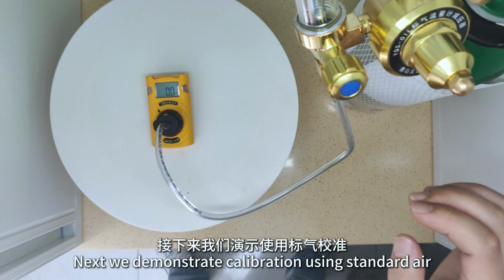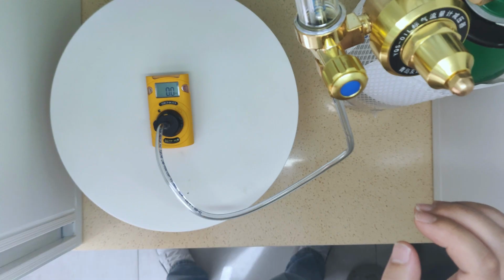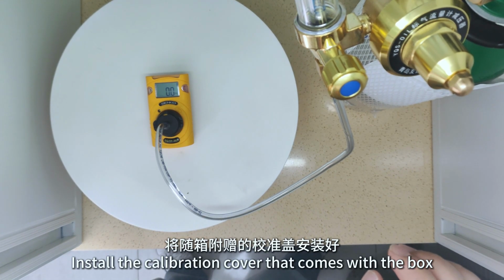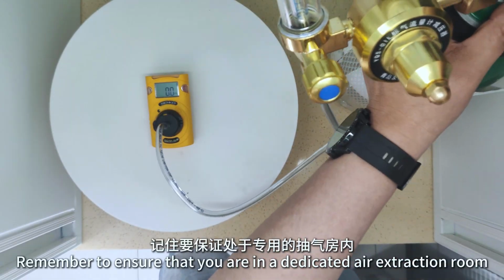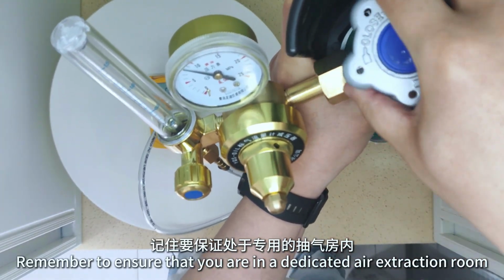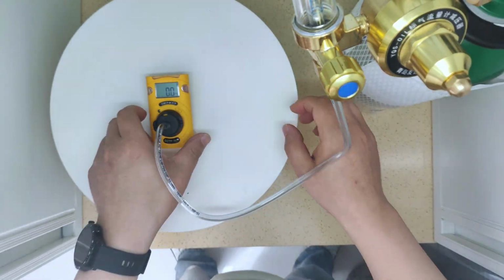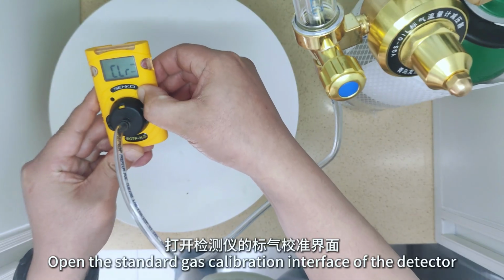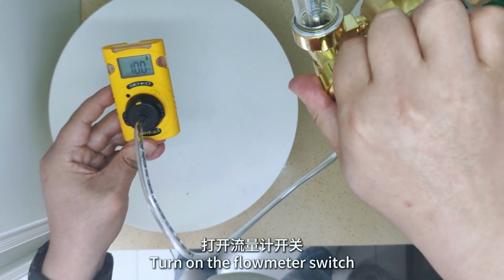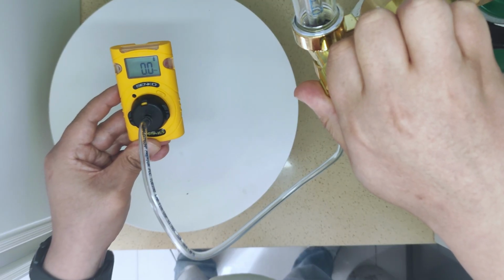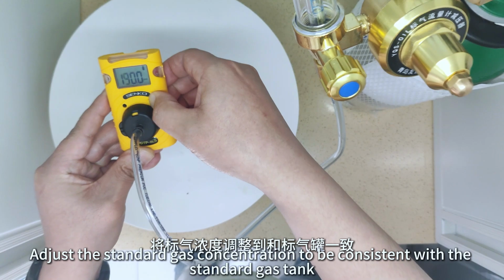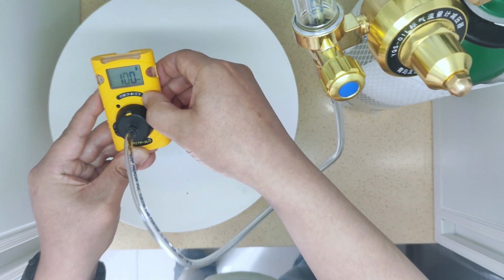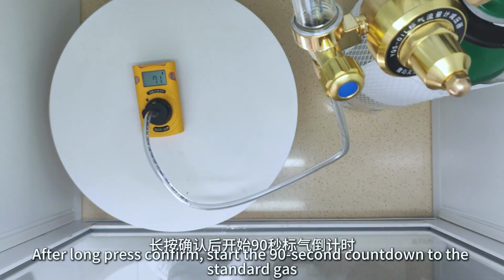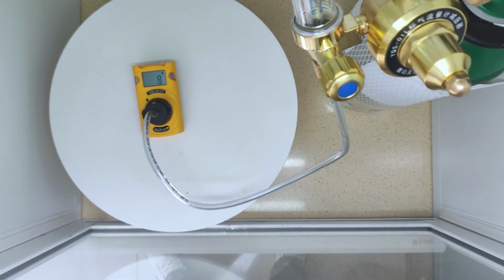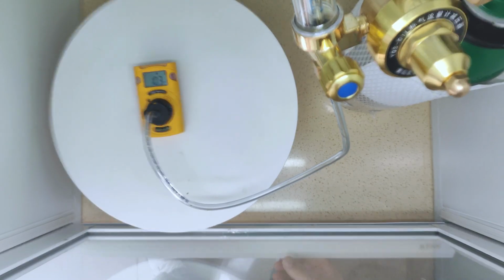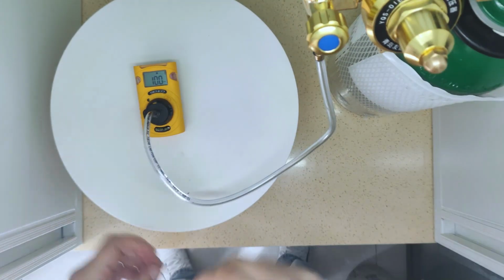Next, we demonstrate calibration using standard gas. Install the calibration cover that comes with the box and connect the hose of the standard gas tank. Remember to ensure that you are in a dedicated air extraction room. Open the standard tank valve first. Open the standard gas calibration interface of the detector. Turn on the flow meter switch. Adjust the standard gas concentration to be consistent with the standard gas tank. After a long press, press confirm. Start the 90-second countdown for the standard gas. After the countdown is over, you can see a small V icon. Close the flow meter and valve. Now our calibration is over.